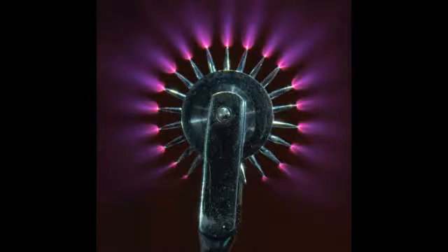A corona discharge is an electrical discharge brought on by the ionization of a fluid such as air surrounding a conductor that is electrically charged. Spontaneous corona discharges occur naturally in high-voltage systems unless care is taken to limit the electric field strength. A corona will occur when the strength, potential gradient, of the electric field around a conductor is high enough to form a conductive region, but not high enough to cause electrical breakdown or arcing to nearby objects.